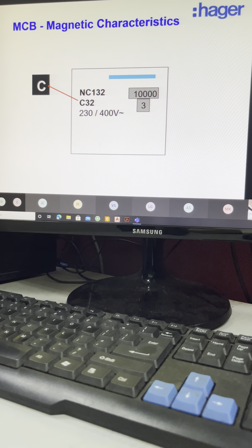That is why when I present on LSIG selection, I start with the BCD curve first. Unfortunately, there is no A. Otherwise, we could start from ABC. But for magnetic curves in circuit breakers, there is no type A, so you start from B, C, D.